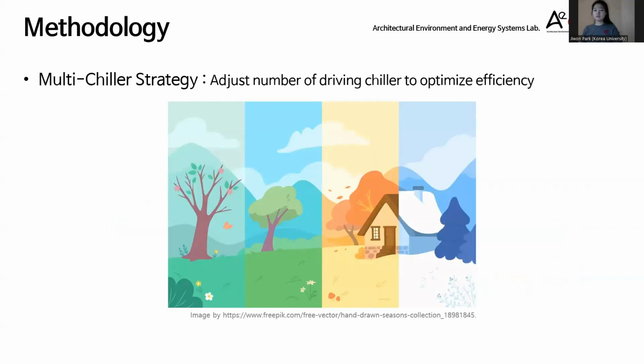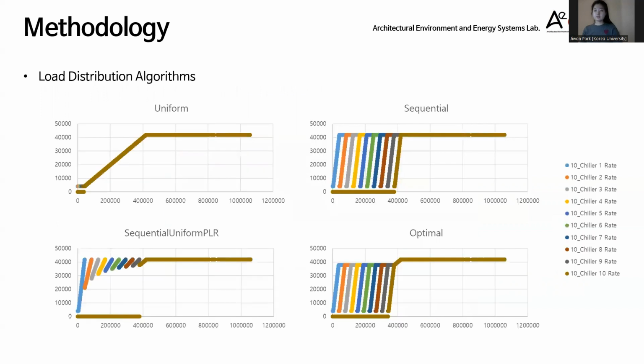Therefore, our goal was to find a way to efficiently operate chillers that experience significant efficiency changes based on PLR even during transitional seasons. We explored the advantages of operating a single building with multiple chillers, where all chillers are turned on during the hottest days, and only one chiller is turned on during days with minimal load, and the number of operating chillers can be adjusted as needed. Additionally, we aim to find the optimal algorithm for distributing the load among the chillers.